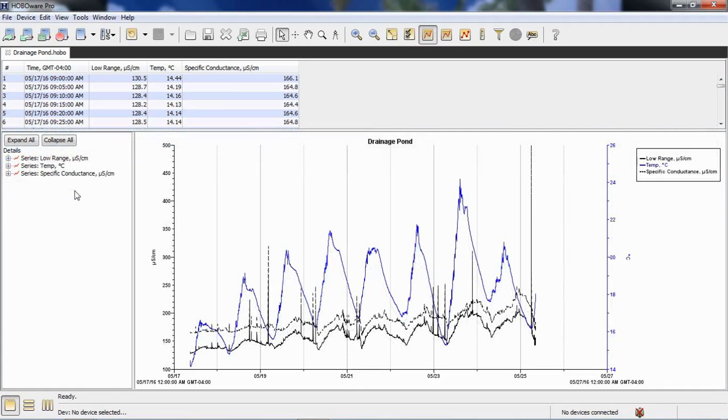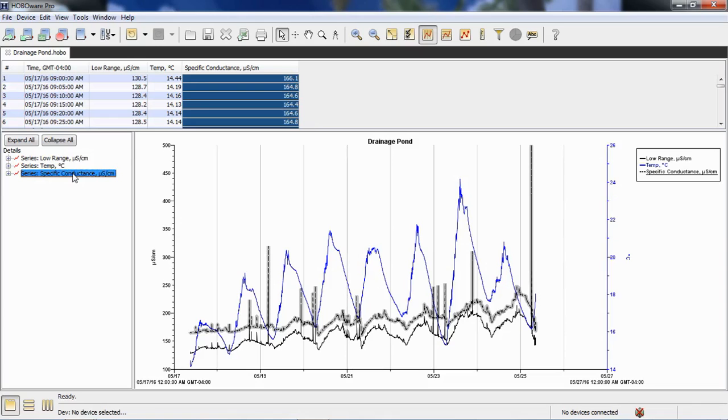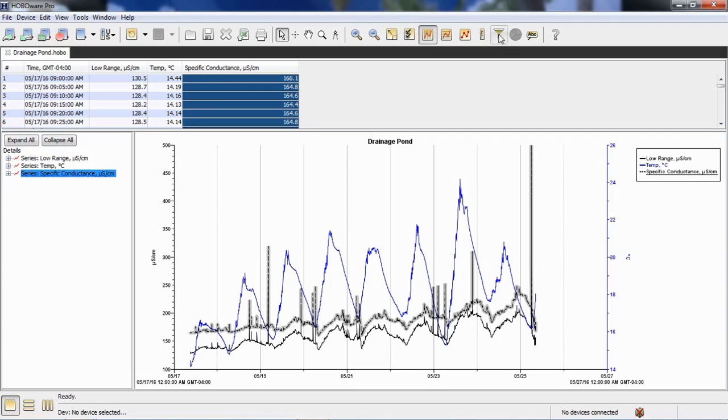As I mentioned previously, you don't want to apply a filter when you're launching a U24 because you need to post-process your conductivity data to get specific conductance or to apply that field calibration to your data. However, you could now apply a filter if you wanted to on your calculated specific conductance. If you wanted to know what the maximum value that you saw each day was, you can click on the little filter icon here or click on edit and filter series.